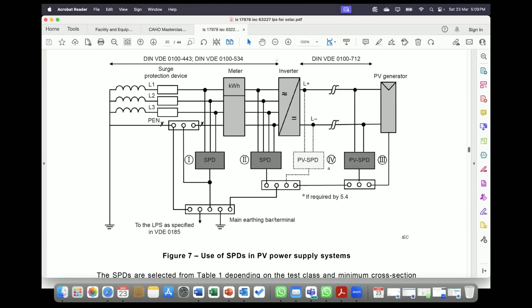The second subject is, once when solar PV, let's say we talk about prosumer installation, the supply is coming from the generator, from the transformer, then sometimes the PV is working in islanding mode. Imagine the supply is coming as a TT system from the transformer, but once it works in islanding mode, the method of achieving safety in islanding mode is different. There, sometimes a different concept has to be made.